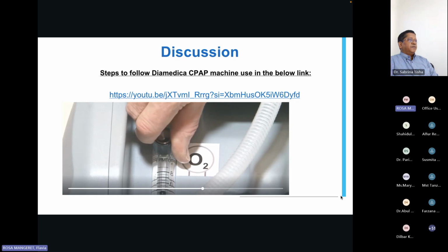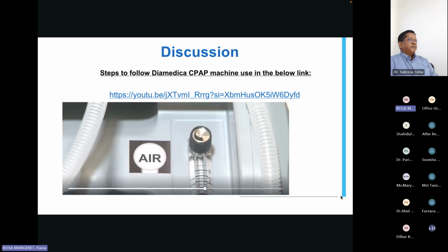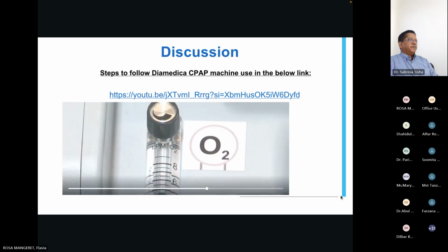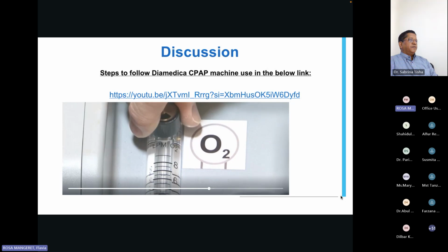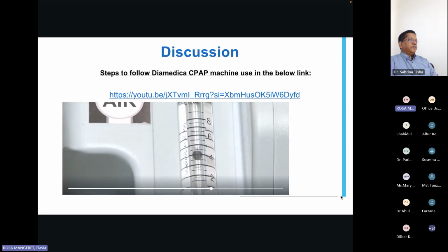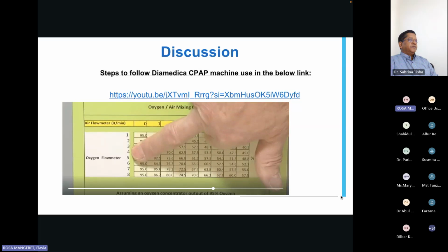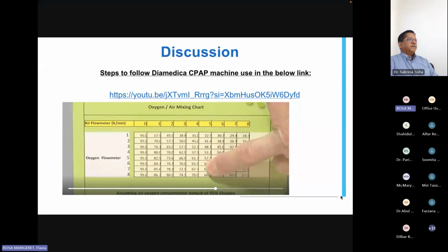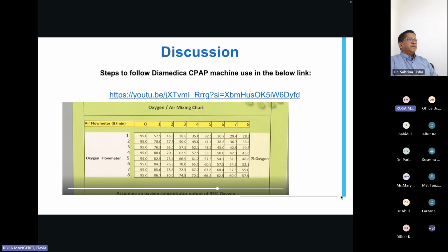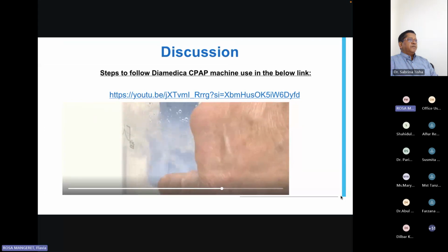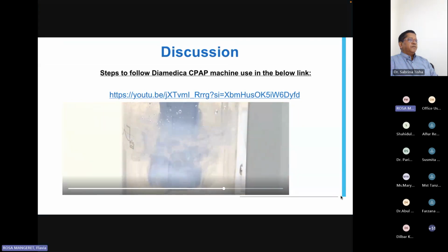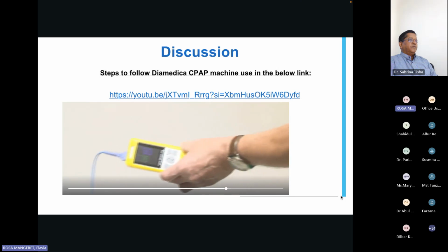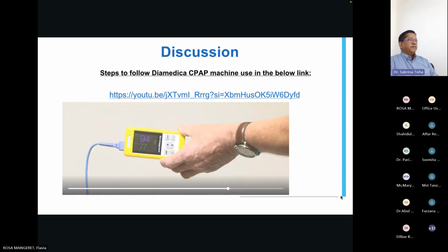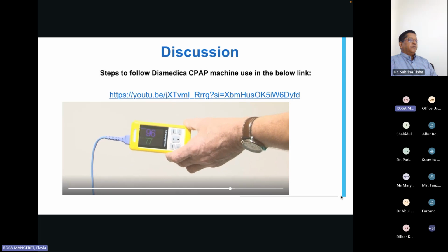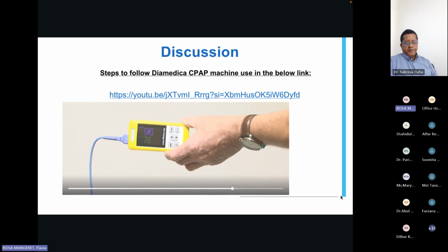Dial the flows of air and oxygen required to see a constant stream of bubbles in the water. Start with 5 litres per minute of oxygen and 5 litres per minute of air. Check and record the flows dialed and the oxygen concentration this provides. A total flow of 10 litres a minute is sufficient in most cases to deliver CPAP, which you can see by the continuous bubbling in the bottle. Check the child for signs of respiratory distress. Check the level of oxygen saturation and check if there are bubbles in the bottle.